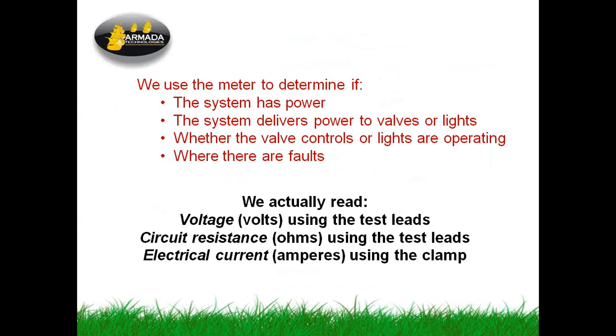It's there to tell us whether the system's healthy. And in the top block there, we're using this meter to determine, number one, if our system has power, is delivering the power downstream to whether they're solenoids on automatic valves or whether they're lighting systems, and determine if the systems downstream from the controller are working. All these things are what we're really after.